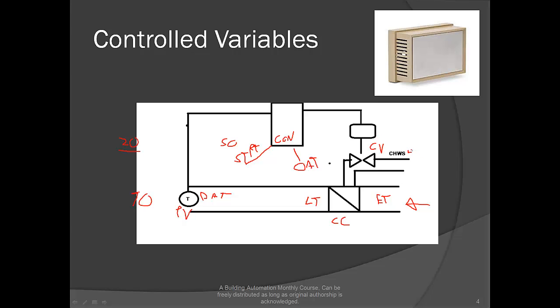A thermostat. What we're looking at here is a simple control loop. We're looking at some control variables: what is called a process variable, a control variable, a controller, a set point, maybe a secondary input looking at outdoor air temp. We've got our cooling coil right here. We've got our entering temperature and our leaving temperature. This is a discharge air temperature sensor. We've got some air flow coming in. And our discharge air, let's say it's at 70 degrees and our set point is 50. Now our controller is going to say, I've got a 20 degree drift.